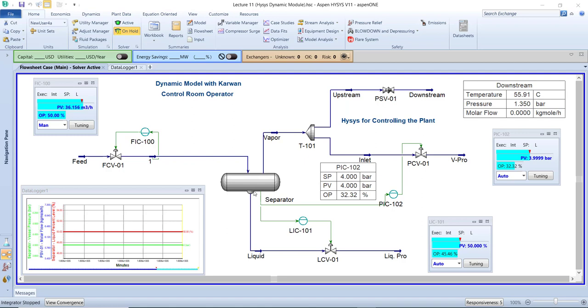The separator performs physical separation — separating the gas from the top and the liquid from the bottom. If there is nothing to control the pressure, the pressure randomly varies — for example 0.5 to 2 bar — and at those pressures you can't get good separation. For that reason, each separator in the world has a special design pressure that helps the process separate gas and liquid perfectly. For example, in this separator the design pressure is four bar; at four bar we can separate gas from liquid perfectly.